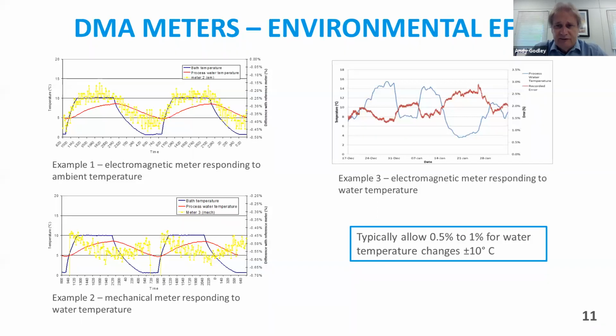I mentioned environmental effects as well. And again, this is something that's not always very predictable. So you've got three graphs here which show examples of test work that we've done. The top left is an electromagnetic meter. This was in a water bath, and we controlled the temperature of the water bath, so the ambient temperature on the outside of the meter. And we could see that the meter responded to that ambient temperature. So the blue line is the water bath temperature, the yellow dots are the meter response, and the difference between an isolated reference system and the meter, and the red line is the water temperature. And you can see quite clearly there that the output from the meter follows the same pattern as the water bath temperature, so the ambient temperature around the meter, not the temperature of the water going through it.